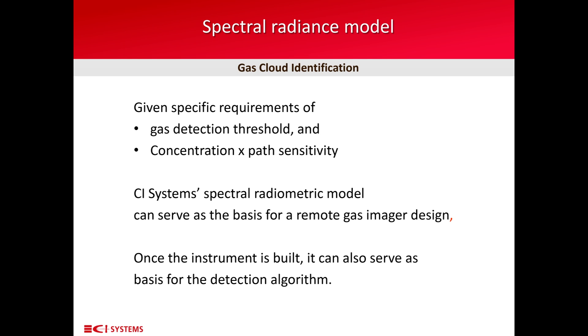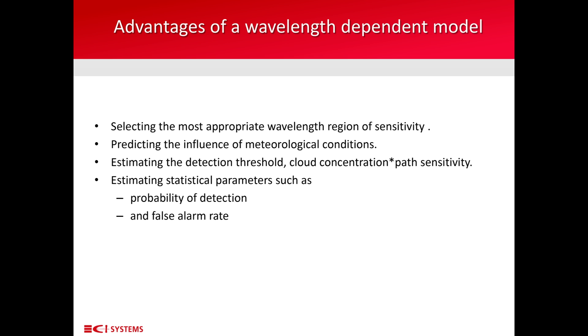Given specific requirements of gas detection threshold and concentration times path sensitivity, CI Systems has developed a spectral radiometric model that can serve as the basis for a remote gas imager design. Once the instrument is built, this model can also serve as the basis for the detection algorithm. The advantage of a wavelength-dependent model is that it allows the selection of the best wavelength region of sensitivity for the specific gas in question. It also allows prediction of the influence of meteorological conditions, estimation of the detection threshold, and estimation of statistical parameters such as probability of detection and false alarm rate.